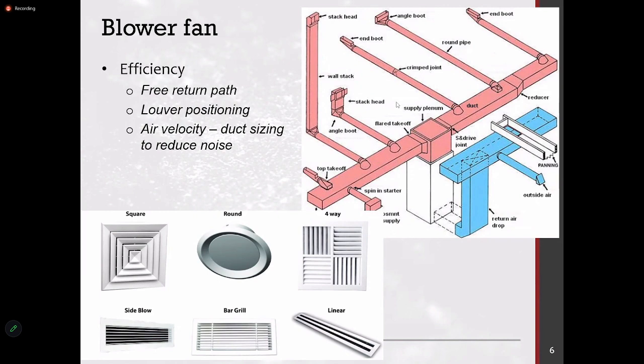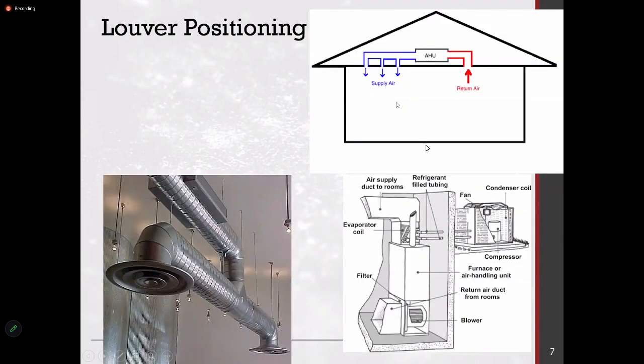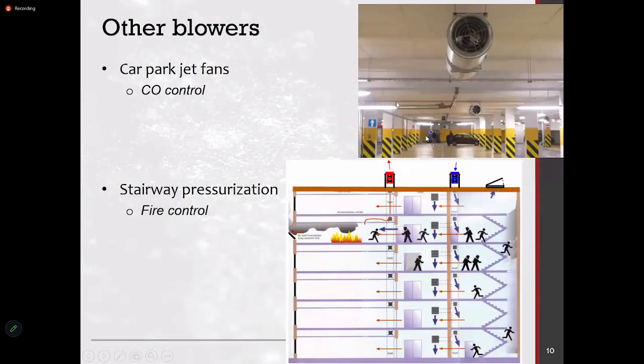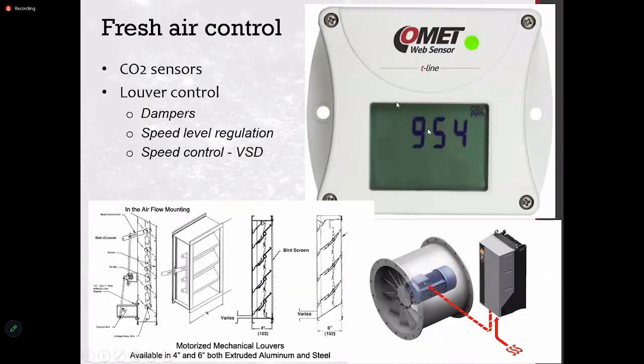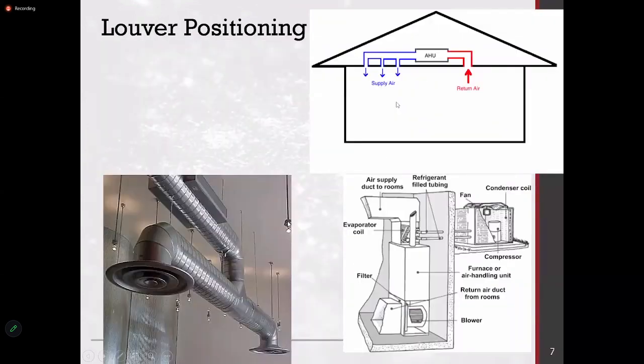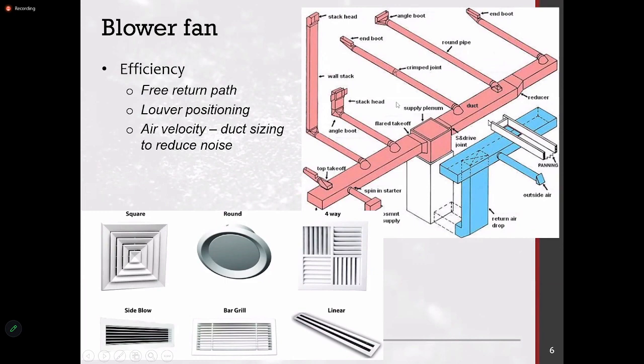So you do a measurement of the airflow, you calculate the airflow rate, and there is a damper behind these louvers. You get a small damper. A damper is like a closure. I have a picture of a damper. Yeah, a damper is something like this basically, where you actually close the space or open the space. So then you can ensure equal air is distributed in every system. So you manually adjust it, and you manually calculate what is the output of each louver.